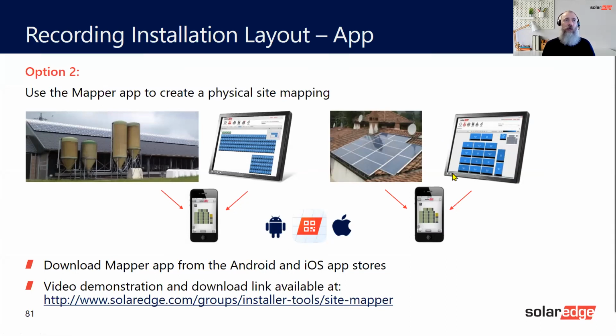You can have as many people as you want on that site using the mapper. They will be able to scan the optimizers and so on. If there's any conflict, it will notify all the people that have scanned the same optimizer. So as long as you're all using different logins, it will be perfectly fine. As many people as you want can be on that site doing it, and it will update automatically. You don't have to press save or update. It will do it automatically.